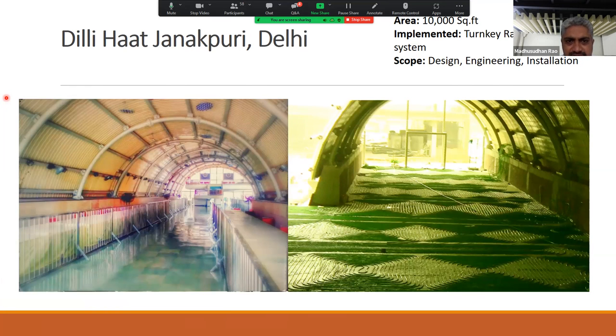This is an exhibition space in Delhi Haat in Janakpuri, where one of the requirements was to keep the space very clean and not have ducts visible. So the sizing of the ducts was to be reduced, and radiant cooling was used to reduce those sizes. The ducts were still used. They are under the floor, and the air delivery is from the sides. So radiant cooling helped achieve better comfort and also better aesthetics in this particular project.